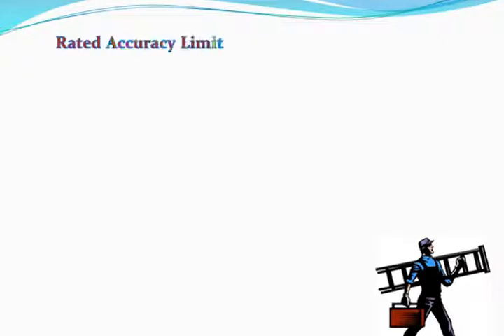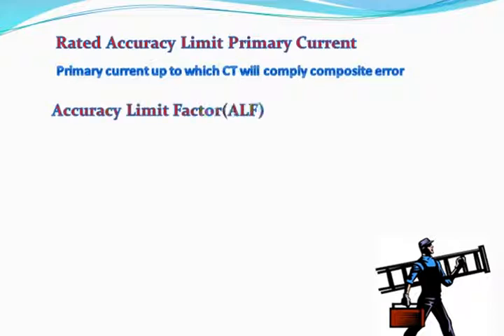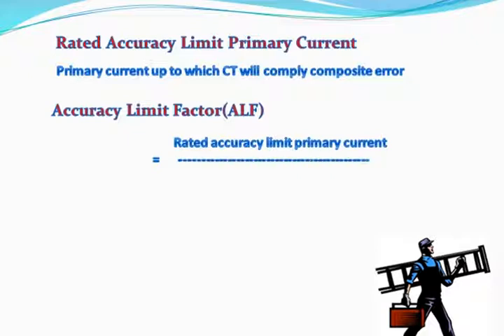Rated accuracy limit primary current: the primary current up to which the CT will comply with composite error. Accuracy limit factor, or ALF, is equal to rated accuracy limit primary current divided by rated primary current.